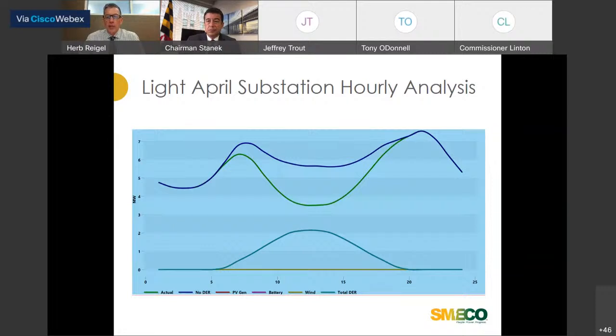So we talked about how system planners need to be aware of what's happening during lighter load periods, as opposed to traditional planning of the past that only looked at system peak values. As solar penetration on this circuit increases, there's a potential during daytime hours that the resultant load on the system will come closer and closer to a net zero value. At those time periods, we need to be concerned and make sure we have proper voltage regulation and no power quality interactions to worry about as a system planner.